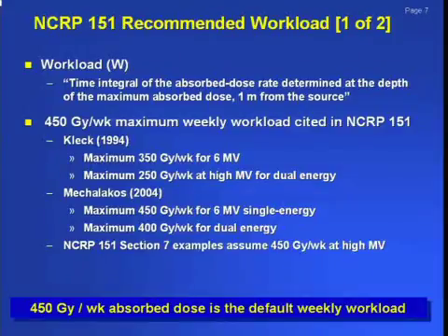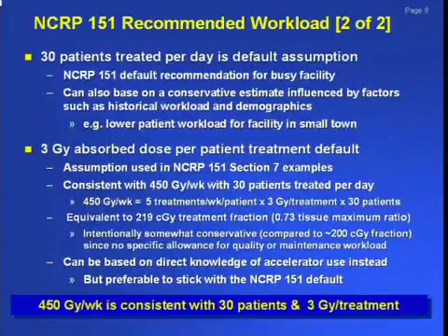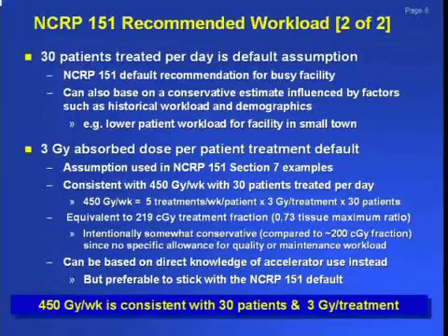But all the example and what I've got in there is that we're using a worst case design of 450 gray per week at the highest energy. That is obviously your most conservative assumption. And yes, that's going to, quote, overshield it, but it doesn't really hurt to have a boring safety survey. I really don't like exciting safety surveys, particularly when I'm standing up there on top of a roof and realize somebody's pointing an 18 MV beam at me, and I hope to heck the contractor built it right.